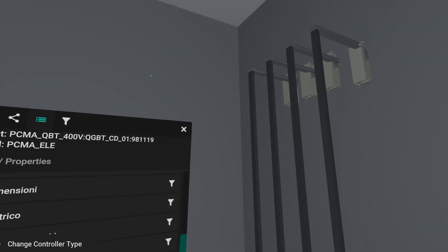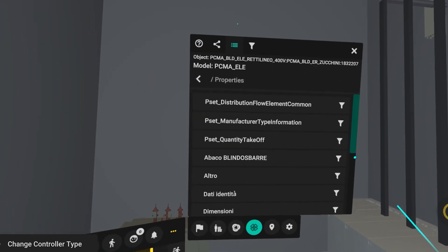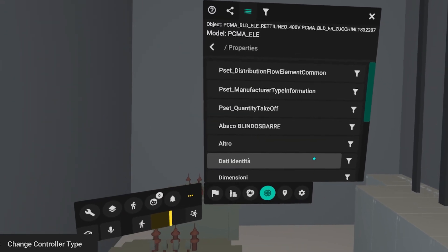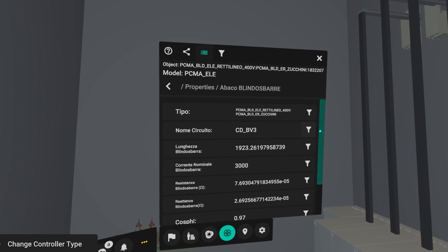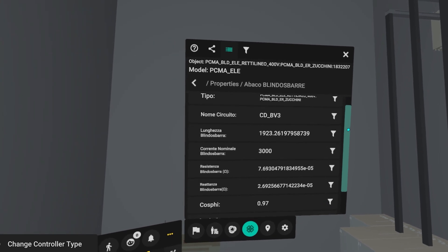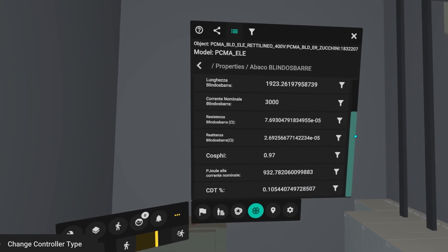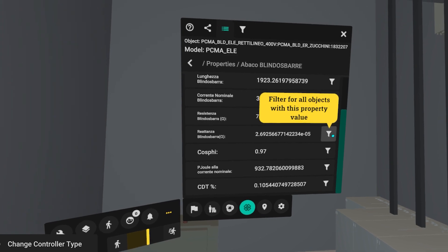The digital and parametric model of the bus bars allows the identification of each individual circuit in the plant. By selecting the component, it is possible to display data such as length, resistance or reactance, but also industrial voltage drop, joule losses and line power factor.